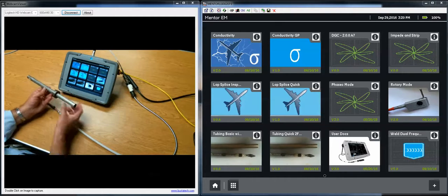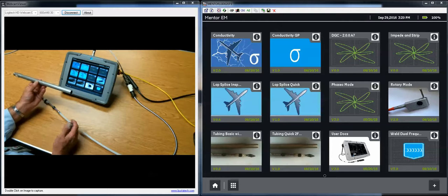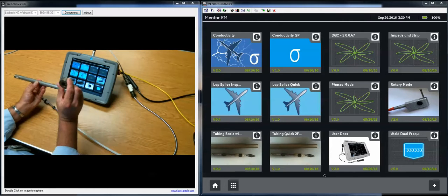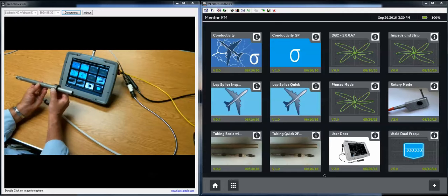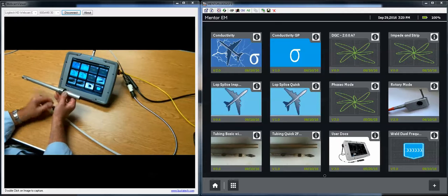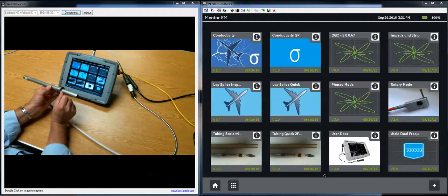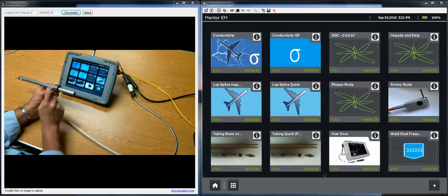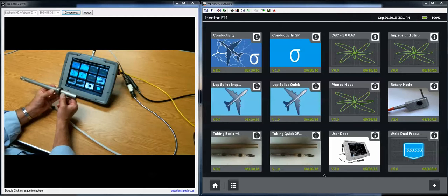In a boiler inspection, we have our boiler tube mounted in a grid plate, with tube supports periodically along the tube. Our eddy current bobbin probe's field will extend all the way through the diameter of the tube and will be impacted. We will see the steel plate that the tube is mounted in, and we're not really interested in that. But if there happen to be cracks right at the edges of the tubes, we'd really like to see the cracks, but we're not all that interested in an indication from the plate itself.